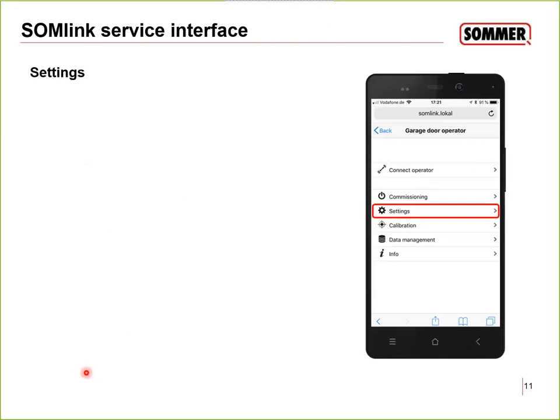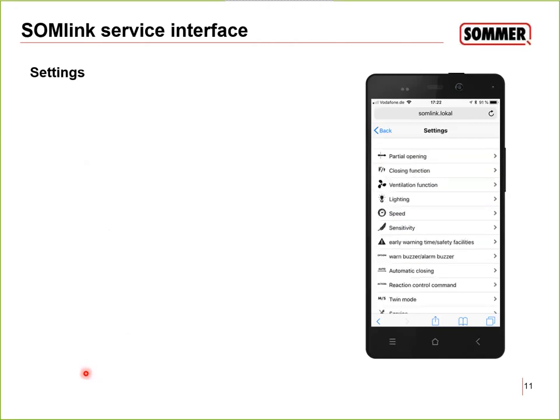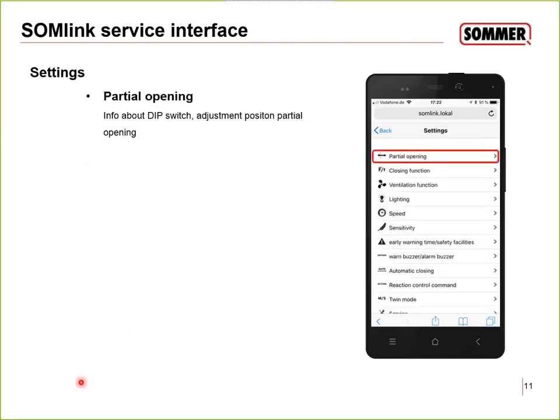Next are the settings. In the settings, there are a lot of possibilities to set up, for example partial opening. You can set up the travel length exactly. So if I want a partial opening of 0.5 meter exactly, you can type in 500 millimeters and then it will run 0.5 meter.